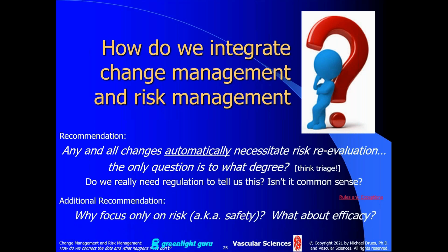My additional recommendation here, and this is well beyond what's in the quote unquote regulation. Everybody focuses on risk, and that's the focus of today's webinar, the integration of change and risk. Well, risk is nothing more than a synonym of safety, right? So I like to say that risk and safety are sort of the opposite sides of the same coin. But where's the discussion of efficacy? If we change our medical device, yes, we have to do a risk reevaluation or a safety reevaluation, if you will.